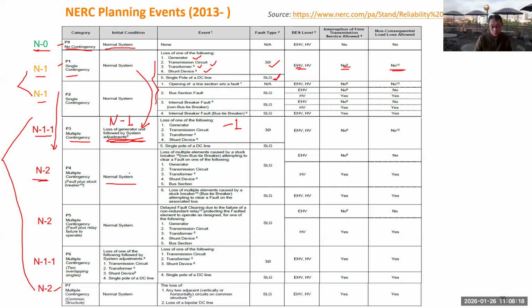For N minus 2, which is based on N minus 0, the contingency is losing any two of the components, and there are also more detailed contingencies. Basically, as a planning engineer, you need to simulate all such contingencies listed in this table, considering all combinations of the devices and components of your system, and check that none of them causes power interruption. If you finish all such study and meet all such requirements, then your system is considered reliable from the planning point of view.